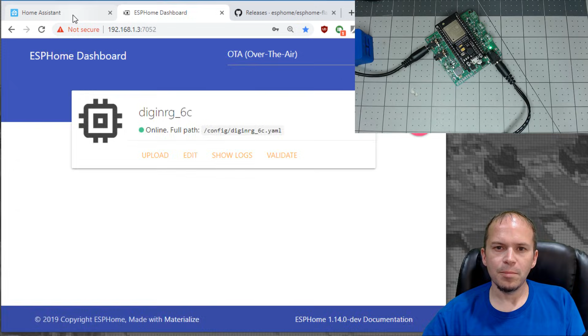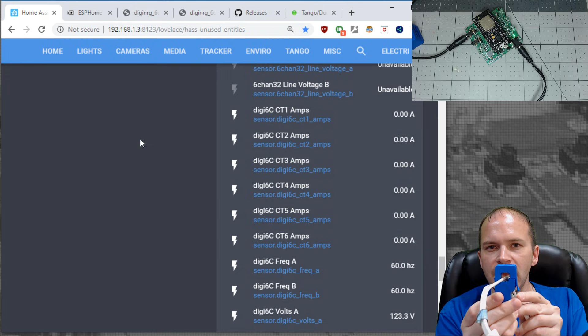Now with CT clamps, you can't just place the entire clamp over, say, an extension cord like this. You won't get a valid reading, or you may not even get a reading at all. What you need to do is just be over one leg. You can't be over the neutral and the load of the wire. This particular extension cord has 3 conductors and you can split them. So whatever you can come up with to get over just one leg of your cord for your calibration, you could just put the clamp over one leg of the extension cord like I've done here. You can see it's just over one leg, and the ground and the neutral are on the other side.